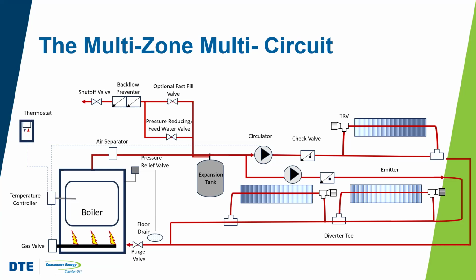But the separate pumps are better because you have individual pumps and not one large pump. Those individual pumps are going to be smaller, so they're going to use less energy. They're only going to operate when their zone, when their branch, is calling for heating. If you have a failure of a pump, you only have an impact to that particular zone. The entire system is not shut down.